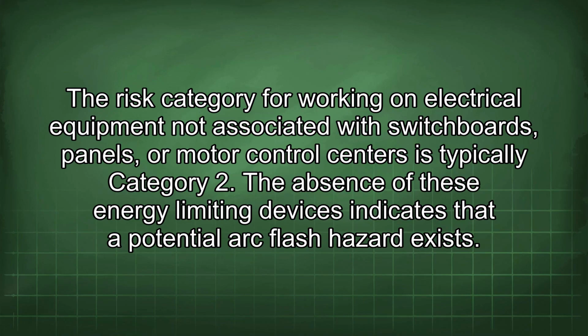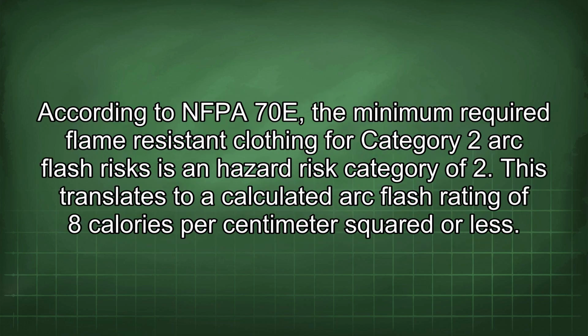The risk category for working on electrical equipment not associated with switchboards, panels, or motor control centers is typically Category 2. The absence of these energy-limiting devices indicates that a potential arc flash hazard exists. According to NFPA 70E, the minimum required flame-resistant clothing for Category 2 arc flash risks is hazard risk category 2. This translates to a calculated arc flash rating of 8 calories per centimeter squared or less.